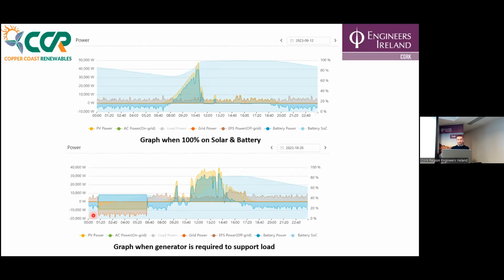And you'll see the percentage of generator running in the next one. The generator then kicks on. So up here, up until 12 o'clock, you can see the site load peaks at 10 kilowatts, probably around 8 kilowatts there. The generator then kicks on, and the generator's at minus 20, because it's charging up the batteries as well as supplying the site load. It then charges the batteries to approximately 40%, I think it's about 38.5, and we kicked off the generator.